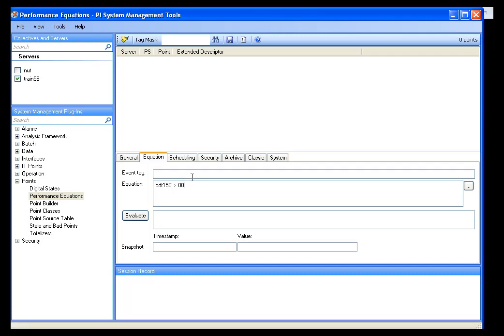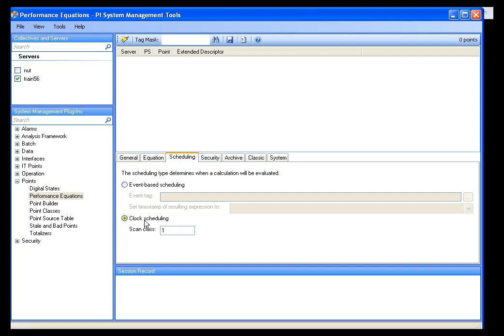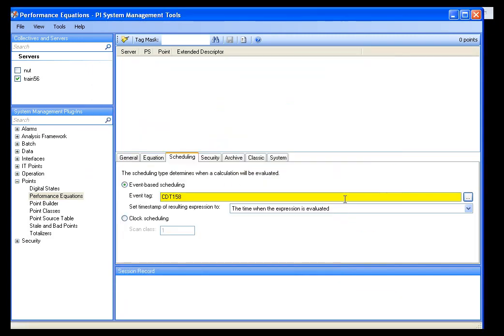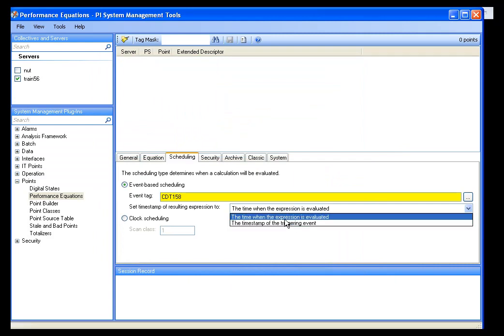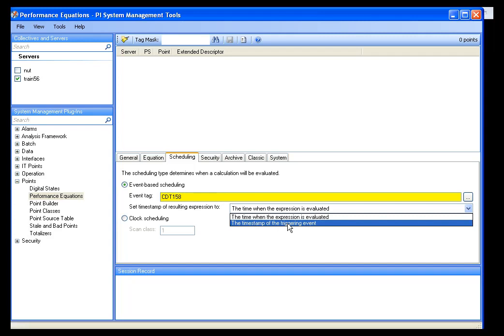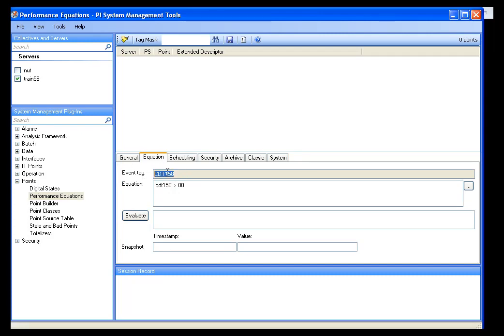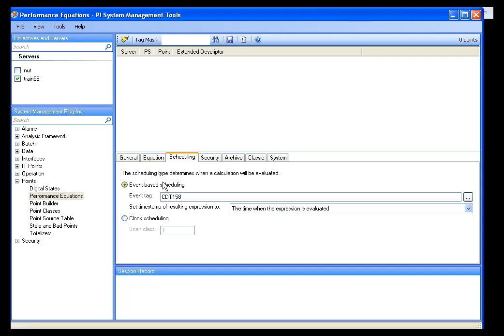The only other thing we need to pay attention to is the scheduling. Do I want to schedule it based on a clock — using the scan classes that are part of the performance equation interface — or do I want to do event-based scheduling? I'll base the event on that tag itself, CDT158. I could have typed it in, but I'm showing you that you can do a tag search here. Then I can choose the time when the expression is evaluated or the timestamp of the triggering event. If you use event-based scheduling, it puts that in the event tag field in your equation tab.